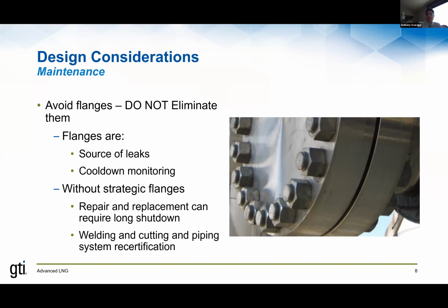As time goes on, if you monitor that, generally, once the bolts and the flanges all cool down together, the leak will stop. The flange will seal up on itself. You can also retorque the bolts if that doesn't occur. All that being said, flanges are a source of a leak in an LNG facility, but they're also critical in being able to do maintenance in a facility.